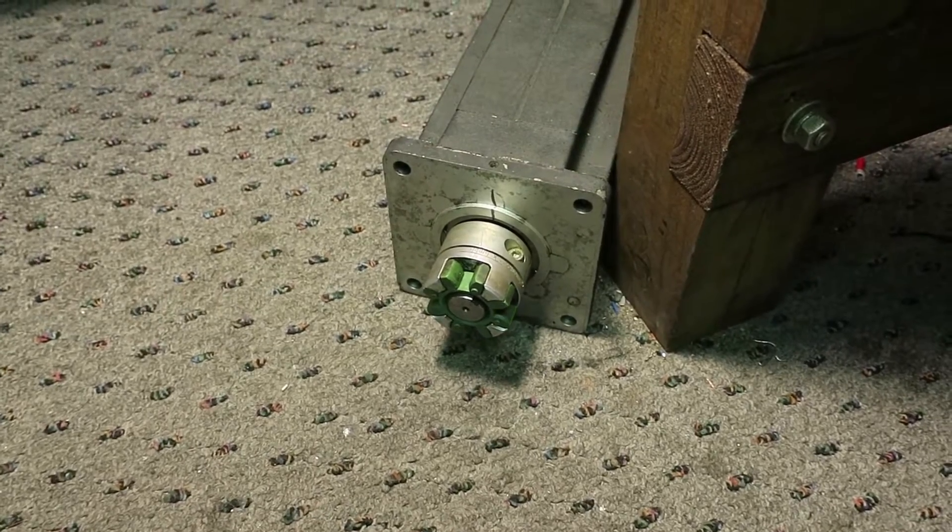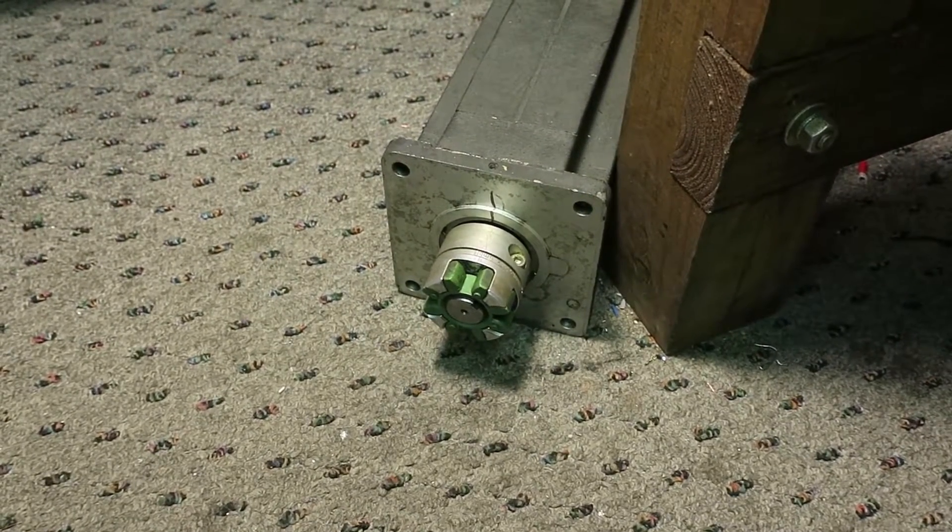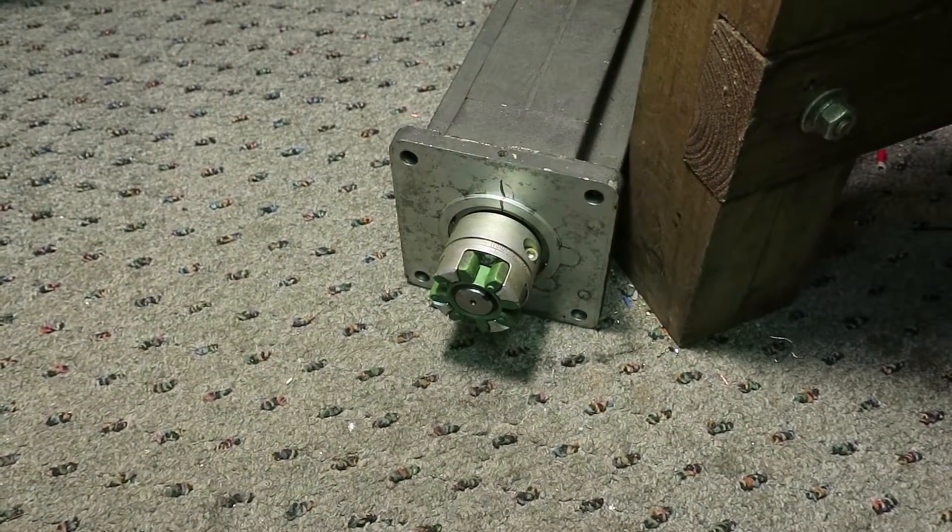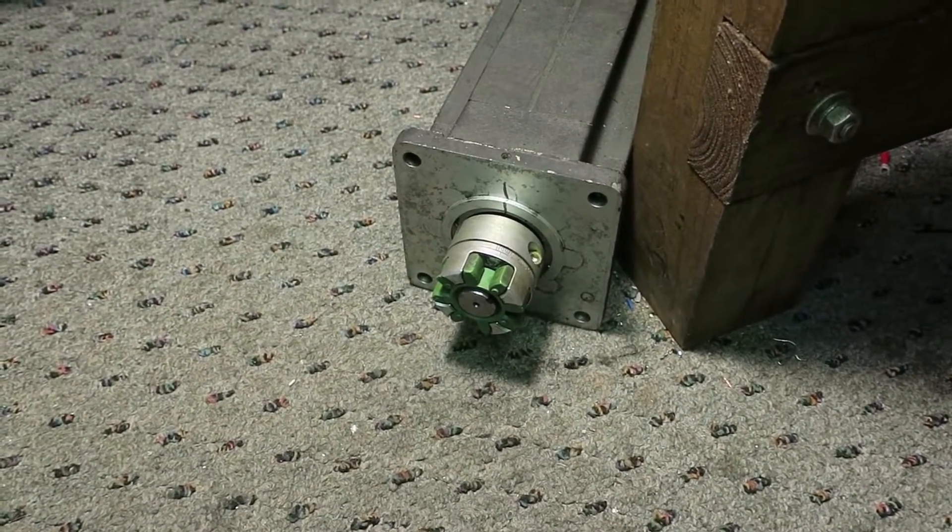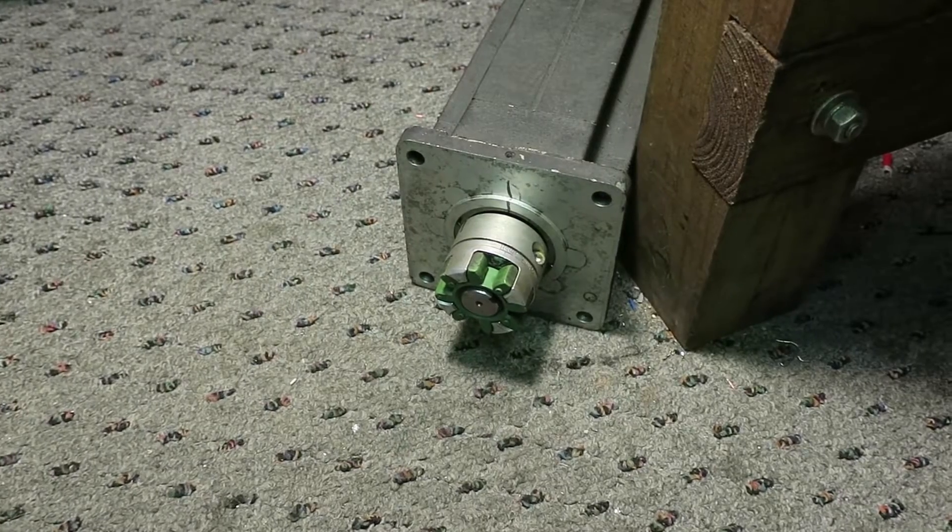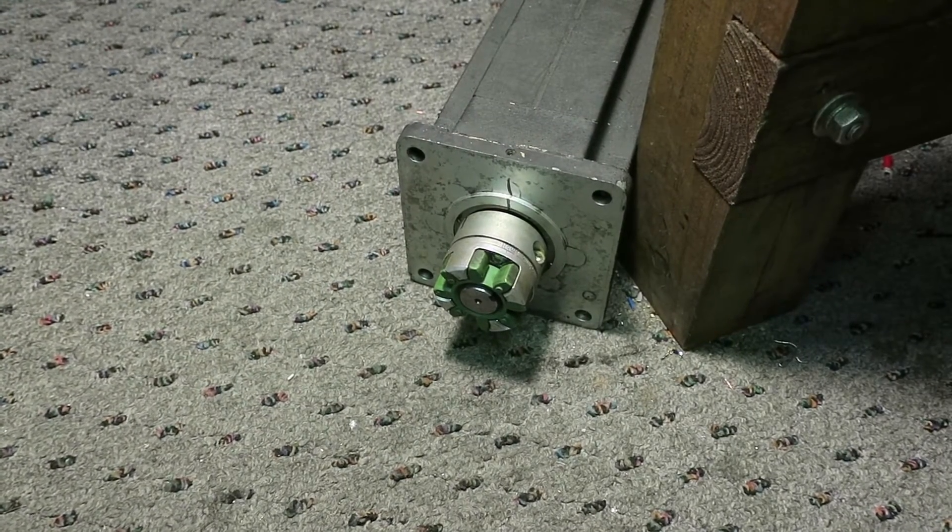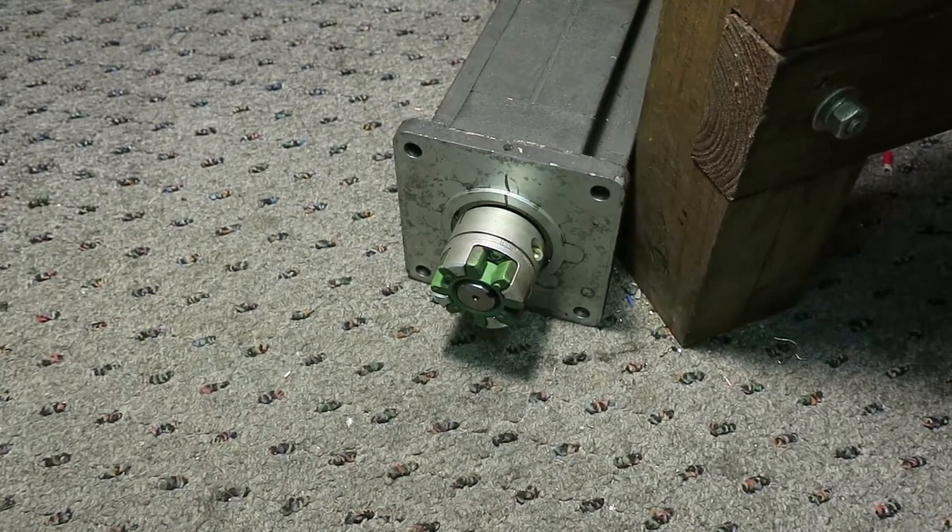So I'm going to go to the servo drive. There's a little balance adjustment pot. And I'm going to turn that until the servo motor, I can actually make it go one way or drift the other way. Ideally, you want to get it set to where the motor is as close to stopped as it can be. That'll make the centroid tuning more accurate.